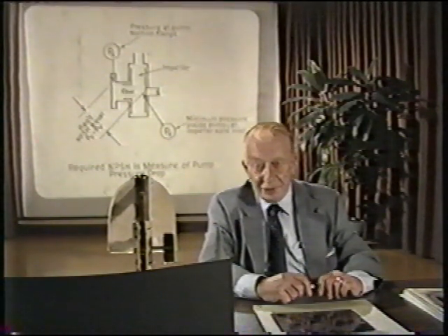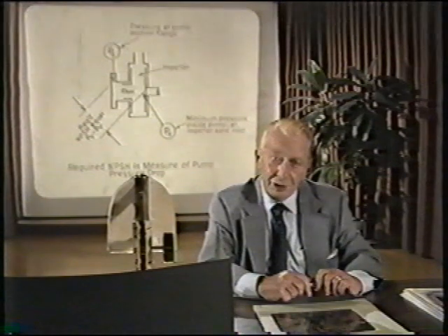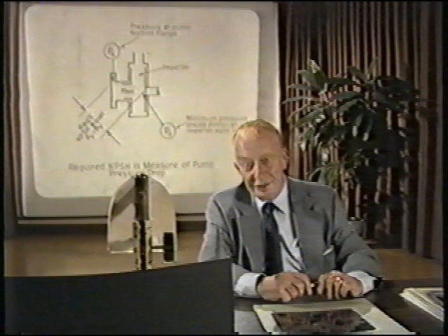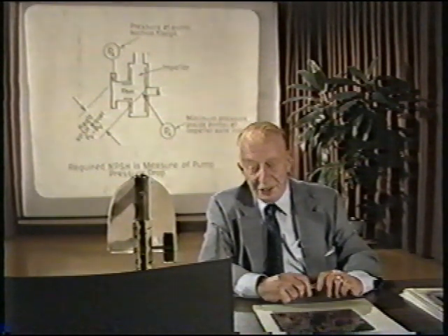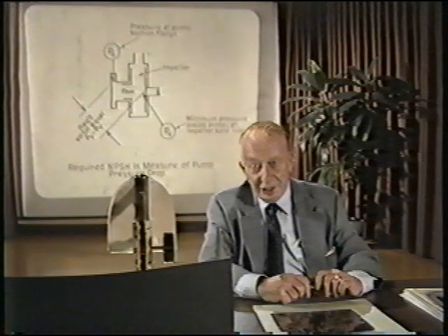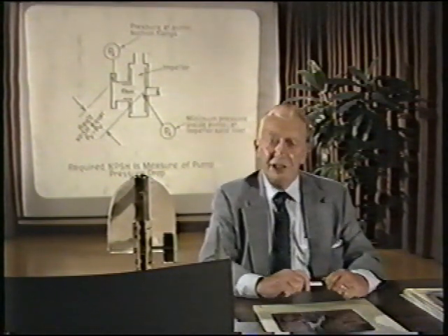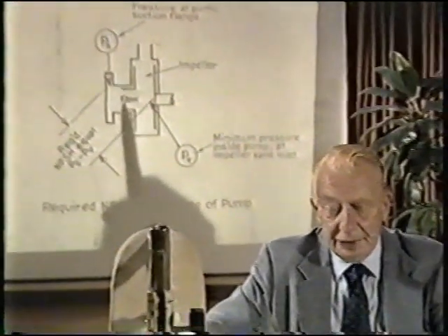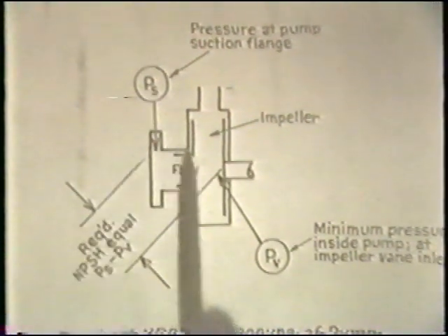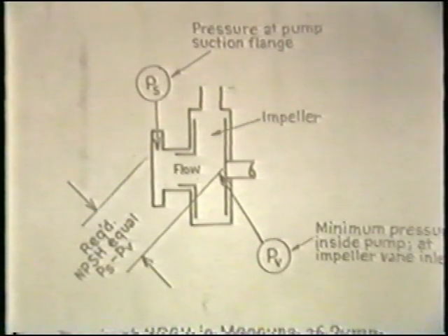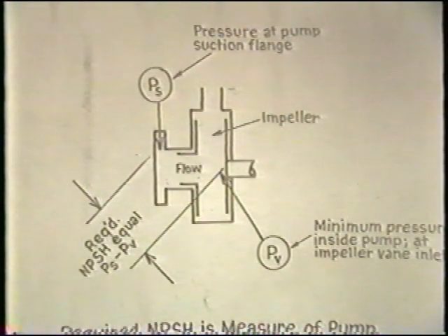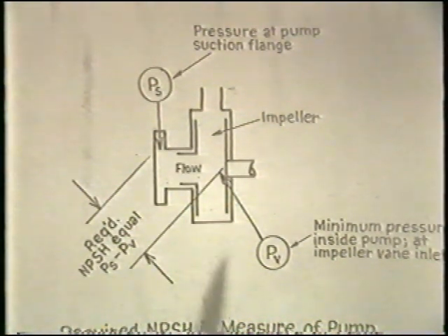but rather on conceptual ideas, as must have been developed when our first engineer, many years ago, developed cavitational problems and the solution to those problems in terms of concept. So let's define the problem. The problem is this: we can have a pump, and that pump can have a pressure available at the pump suction flange over and above the liquid vapor boiling point. So it would appear that the pump should work satisfactorily.